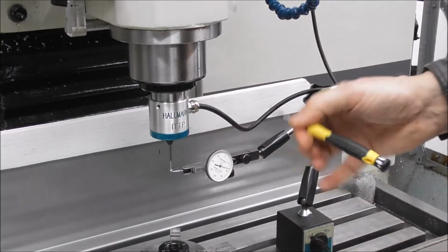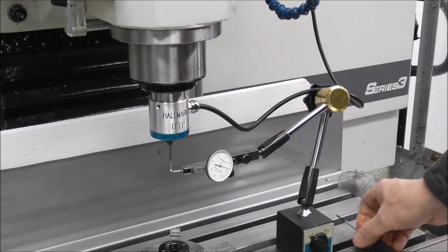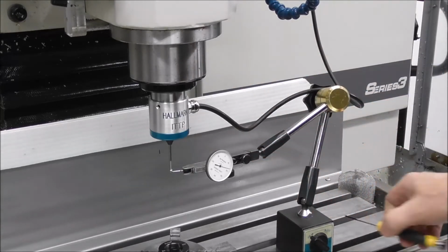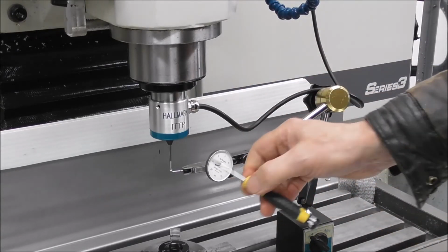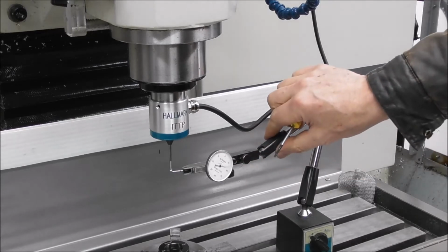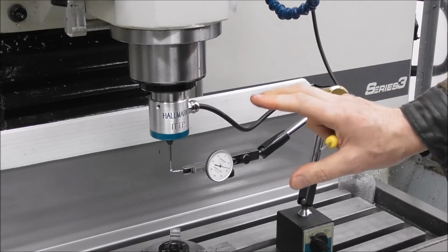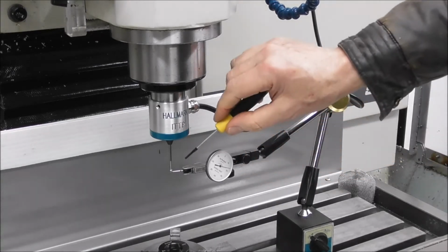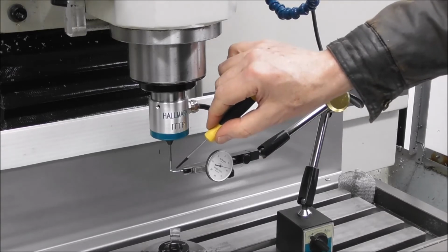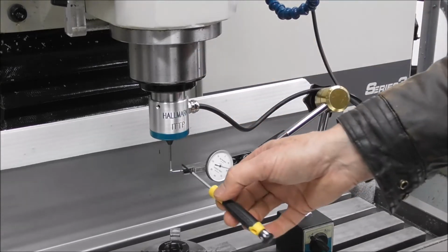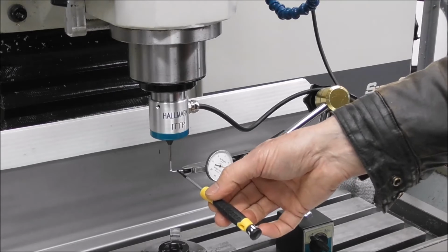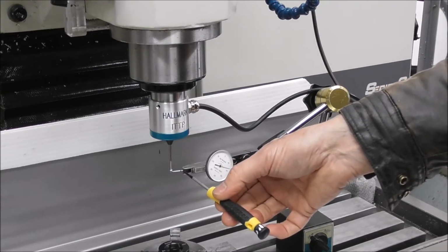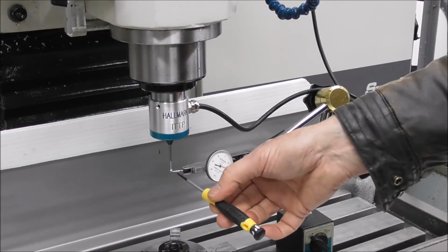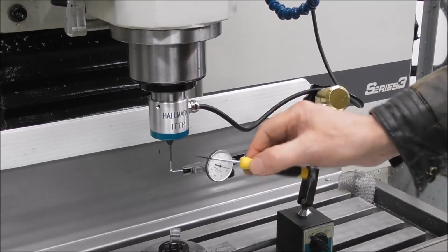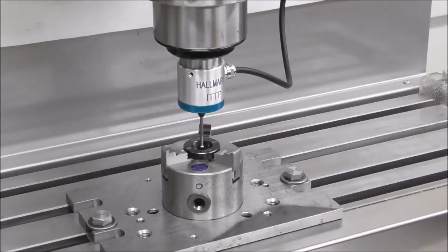I won't try and get it better than that on the video because it's a bit awkward to get at with the camera going, but you just finally snug down those screws until you get it as close as you can. And you can never get it perfect because of a change in direction and the flex of the stand of the dial indicator, any errors in the dial indicator, especially if the little stylus is loose, check that's tight. You'll get all sorts of difficulties if you've got looseness in the stand or in the needle.